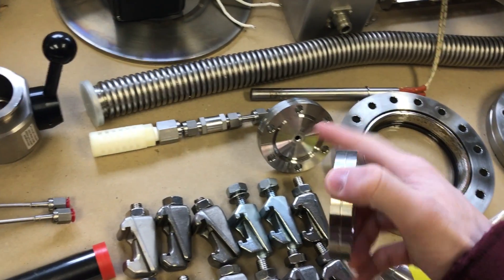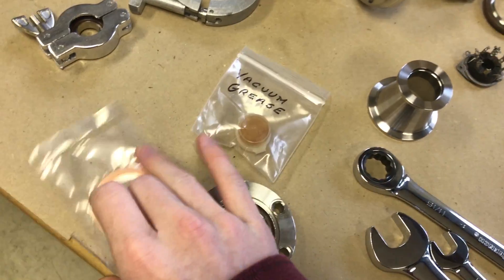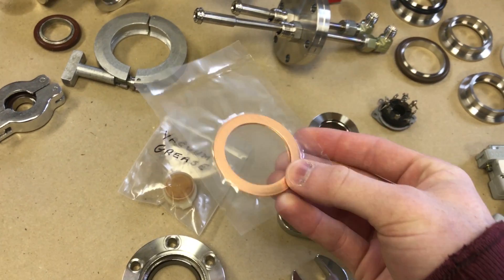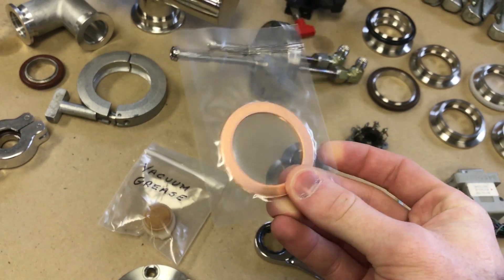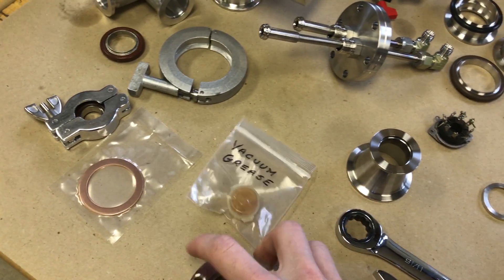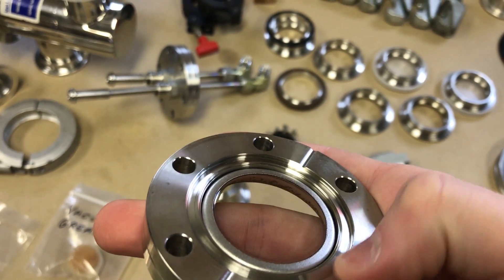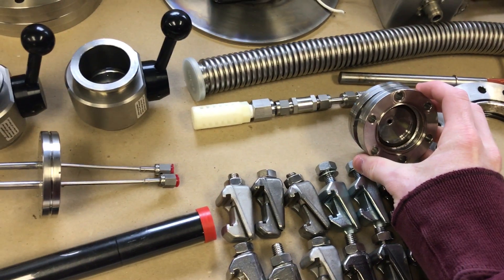So if this were the chamber end, it would bolt on like that. And you would sandwich a copper gasket in between them. It's an oxygen-free copper gasket. And these get pretty pricey as these conflats get larger. And that would get pressed in by this knife edge in there. And it would create a very, very good high vacuum seal.